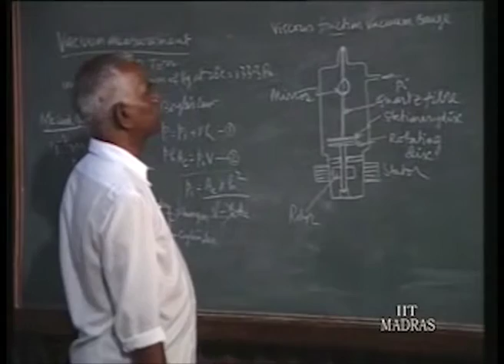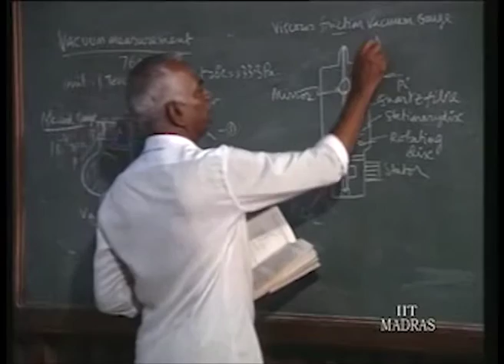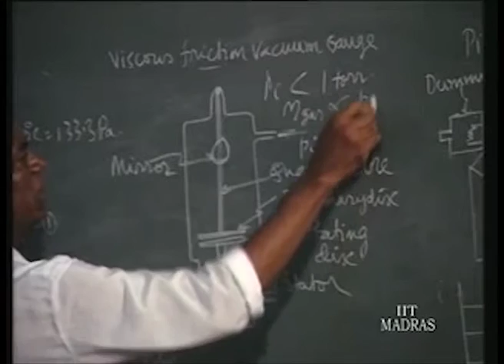The second method is the viscous friction vacuum gauge. Whenever the pressure P1 is less than 1 torr, the viscosity of the gas is proportional to the pressure. The absolute viscosity eta of the gas is proportional to P1. The higher the pressure, the higher the viscosity. That is what is made use of here.